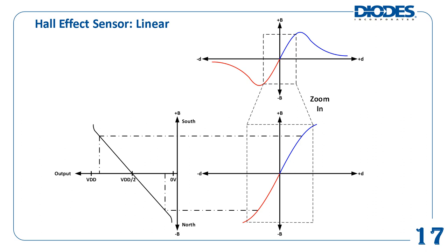An application example that can use the linear Hall Effect sensor is in valve position sensing. Usually a two-pole ring magnet is used in conjunction with a linear Hall Effect sensor. As the valve opens or closes, it rotates the attached ring magnet. The rotation of the ring magnet changes the magnetic flux density detected by the linear Hall Effect sensor, which outputs a voltage proportional to the flux density. This voltage is fed back to a control system so it knows precisely how opened or closed the valve is, allowing the system to more accurately regulate the amount of substance flowing past the valve.